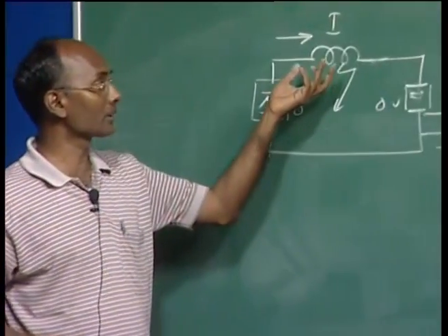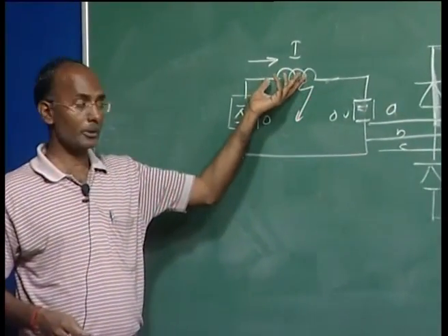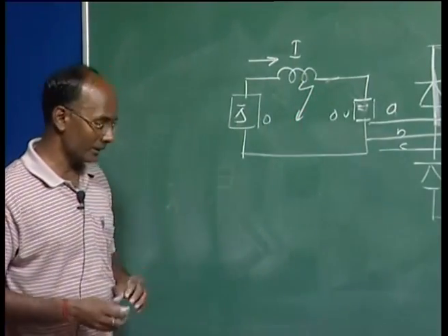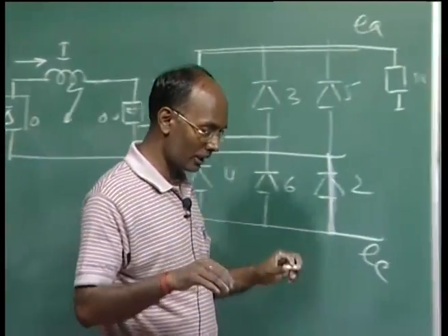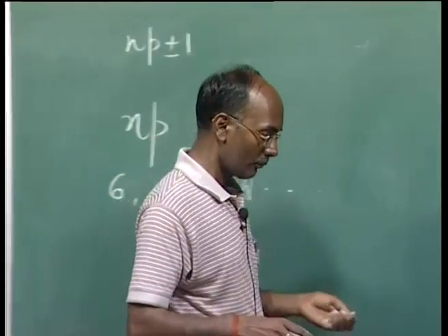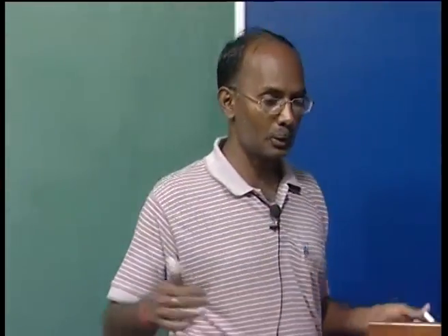Then I discussed the smoothing reactors and their purpose. And finally, I discussed the grounding rods, which are used in emergency conditions, where we can use the ground as a return path so that the lower level of the earth provides minimum impedance. And the transmission line, as I said, is not very special. It is just like a simple HVAC transmission line, and the voltage level, etc., is decided based on techno-economic considerations.